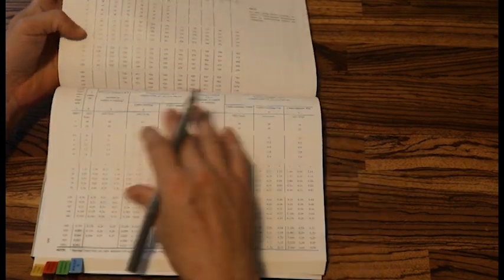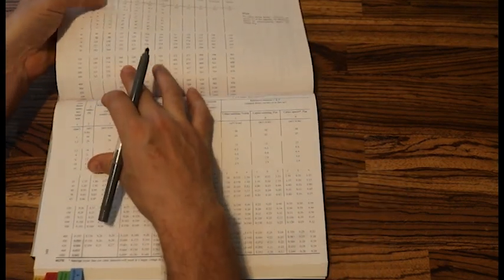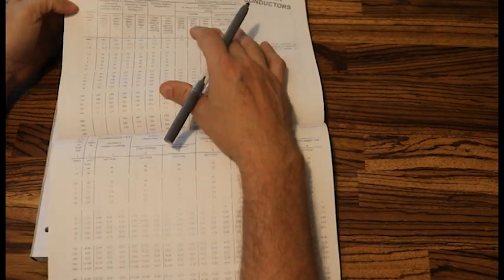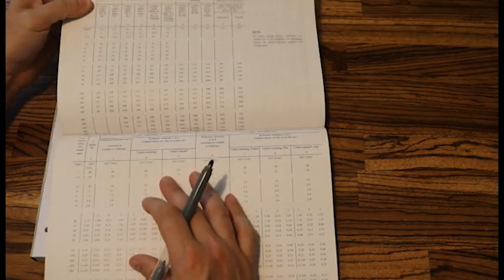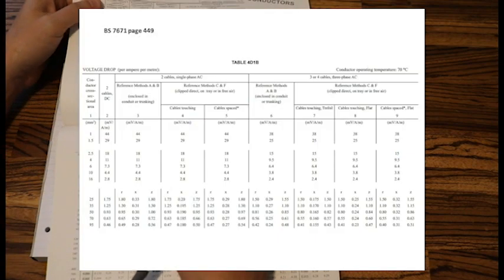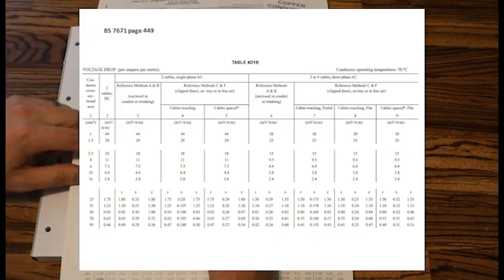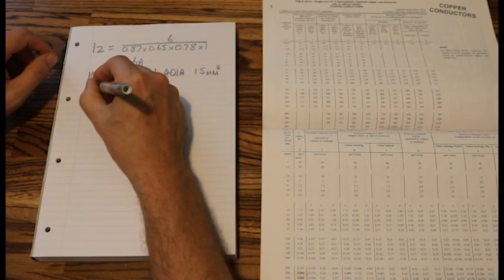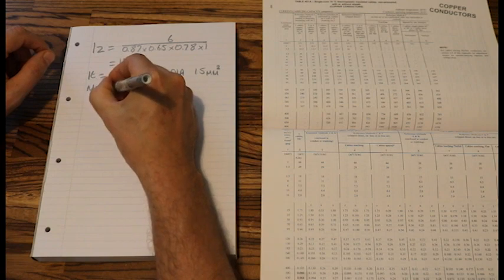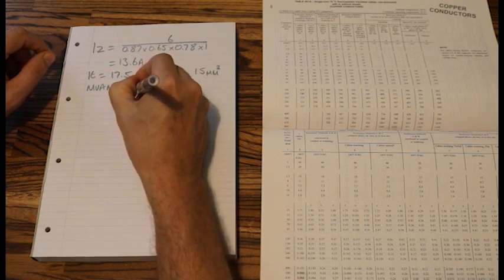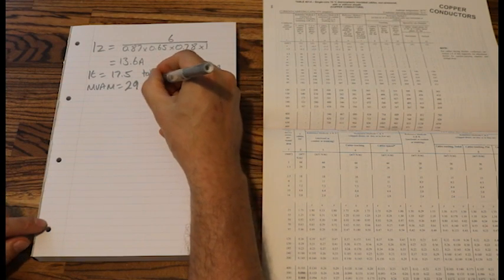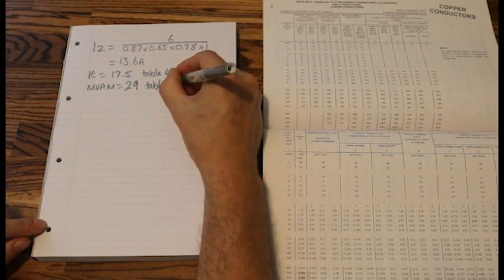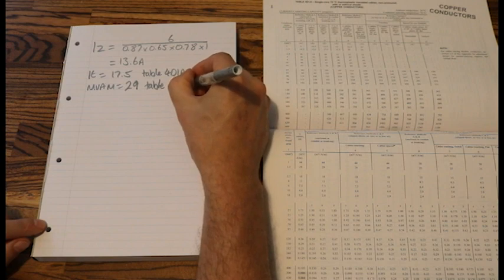And we go back, we now need the NVAM value. So these tables come as a pair, this is our IT table, here is our NVAM value. We are reference method B, enclosed in trunking, so we can look at this one, column 3 says 1.5 mil cable, NVAM value is 29. So we can now write NVAM equals 29, reference to table 4D1B.